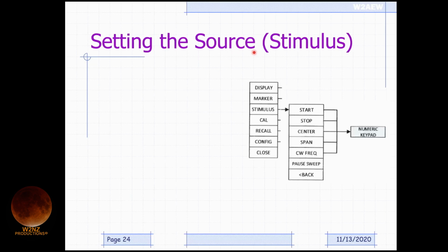Setting the source or the stimulus. This is to set the frequency range that we want to make measurements over. You go down to stimulus, and you can pick whichever is easier by setting the start and stop frequency. Sometimes that's easier if we want to measure over a particular frequency band, say 14 megahertz to 14.3, for example.